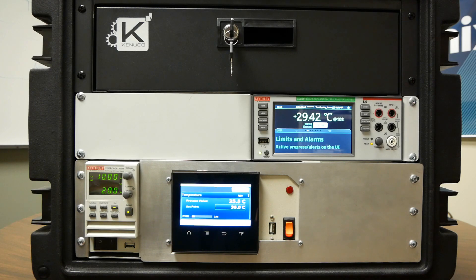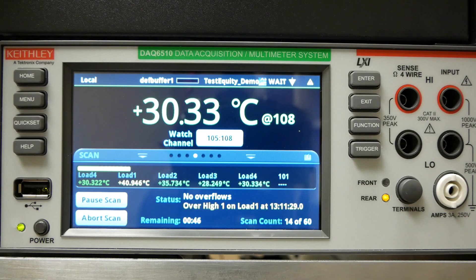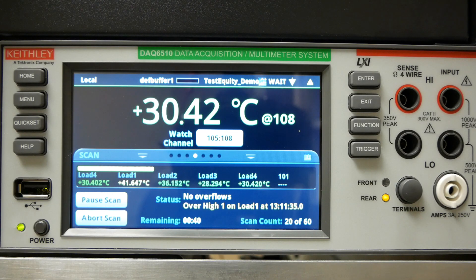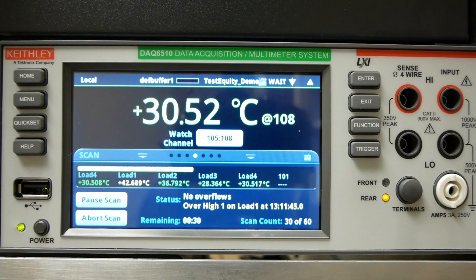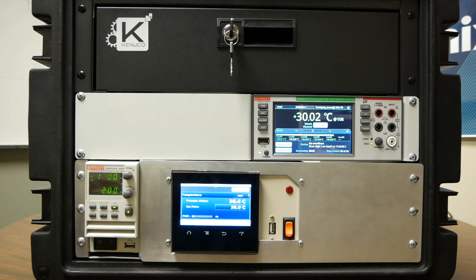Here we're going to see the limits and alarms function that the DAQ6510 has. Each time that the scanned value goes above whatever limit you set, it will highlight a point on the status bar as being yellow rather than green. It will also give you a little error message — for example, it says "over high one on load one" at whatever time. And that will continuously update to the latest alarm that has been tripped, so you can get an active view of what's going on in your scan as a whole while it's going.